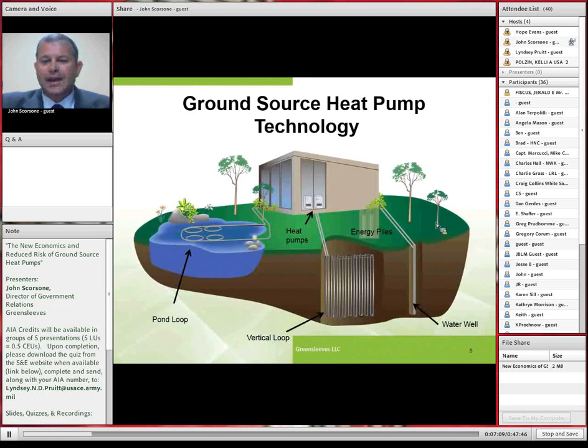Also shown on the slide in a light color underneath the building is something known as energy piles. These are relatively new technology. Since the vertical support columns for a building require holes to be dug, why not add loop pipe into those holes and use the earth area nearby for heat exchange? Not that the energy piles would serve your entire building need, but they certainly can lower your borehole drilling costs. However, the most common approach to ground source heat pumps for commercial buildings is the use of vertical loops, known as boreholes, that are installed nominally 100 to 500 foot deep.